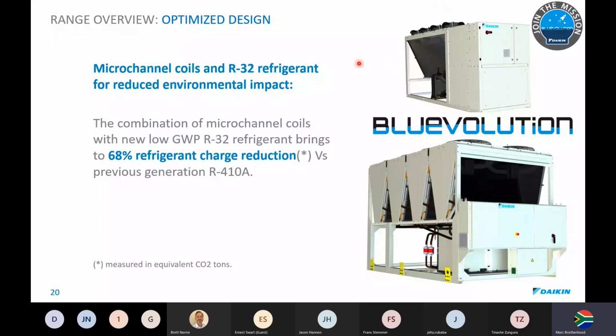So the microchannel coils and R32 refrigerant, why we use them is to reduce the environmental impact. If we look at the combination of using a microchannel coil as well as our new R32 refrigerant, it brings around a 68% reduction in refrigerant charge versus a previous R410 chiller. So we're using up to 68% less refrigerant by changing the coil material as well as changing the refrigerant. So for environmental purposes, it's a huge advantage using R32 refrigerant in combination with aluminium coils.